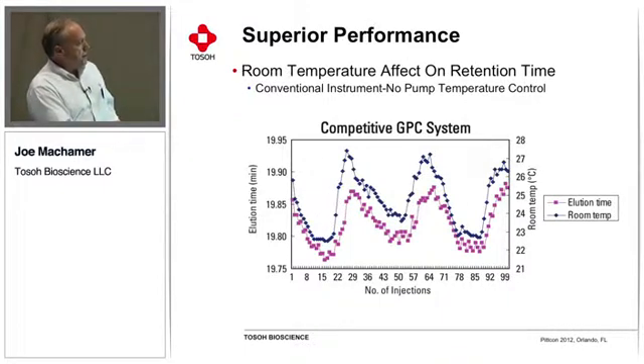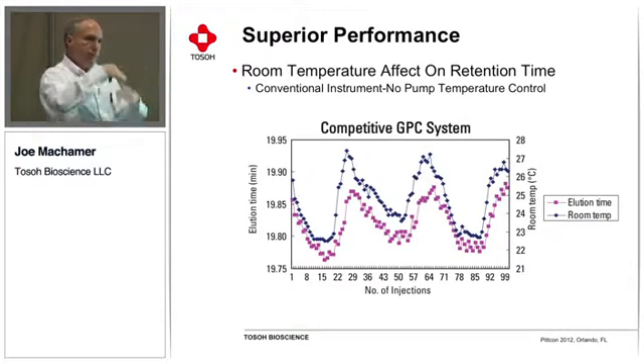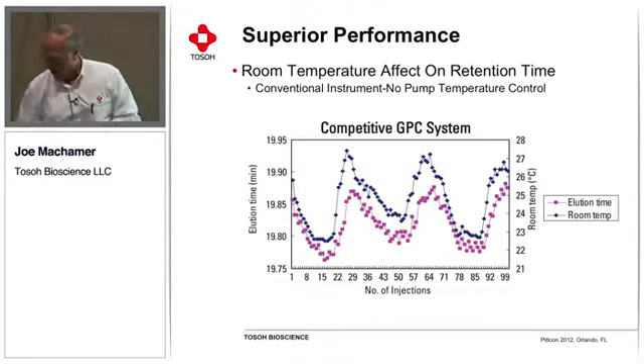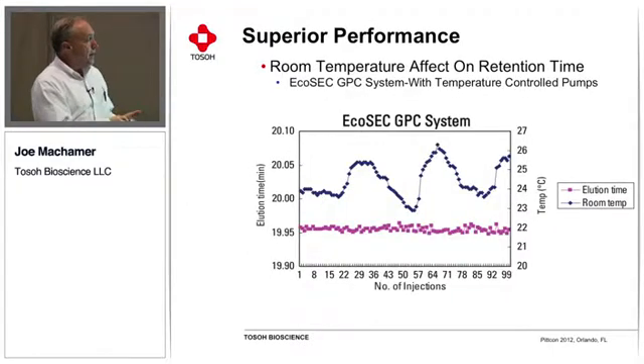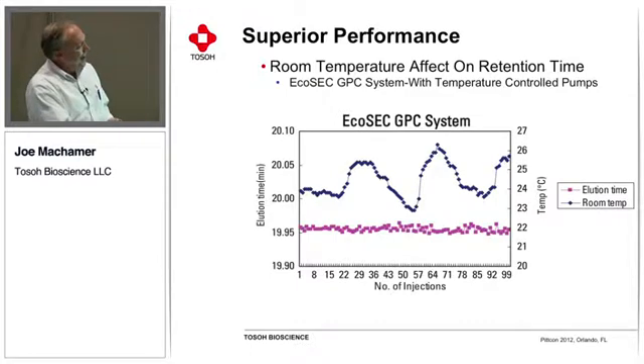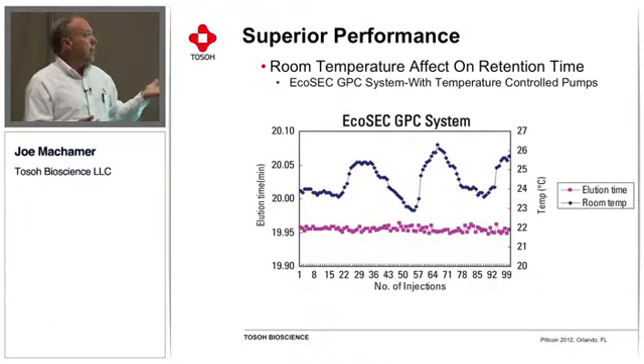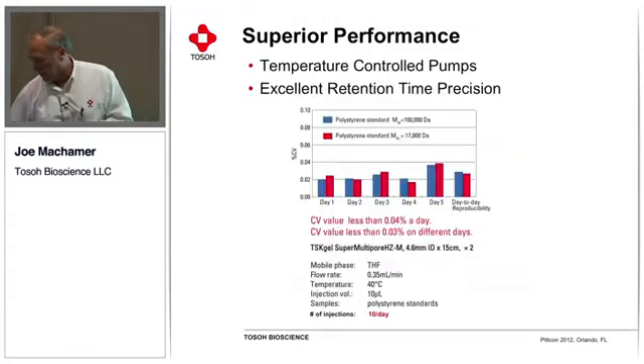On a conventional system, you can see how the change in the temperature of the room is affecting the elution time of the molecules. They're completely in sync with one another. However, if you do this same experiment with the EcoSec GPC system, the temperature in the lab is changing because we're intentionally doing this, but the retention time and elution volume for the sample remain constant. That's because the instrument has an oven system that keeps the pumps at a constant temperature. So if you have any swings of temperature in your lab, they're not going to have any effect on the precision of your GPC analysis.